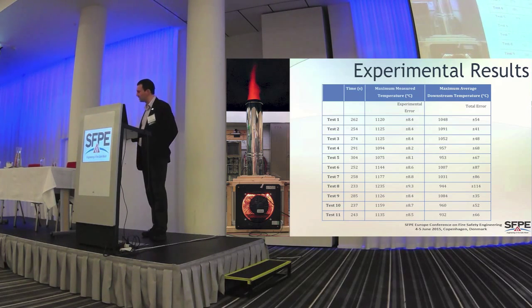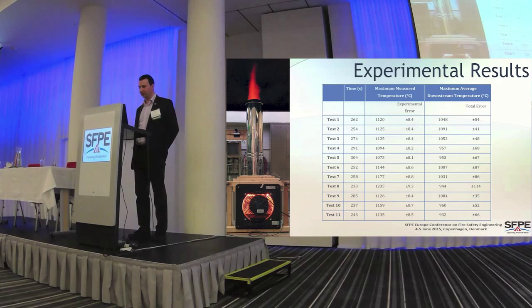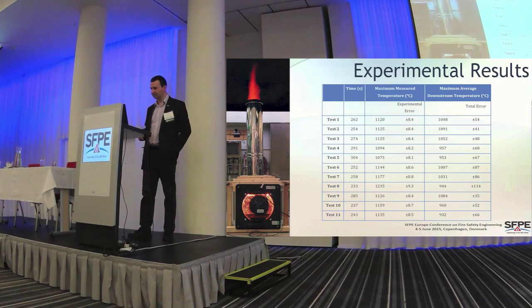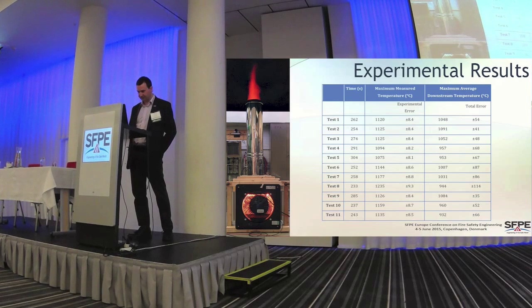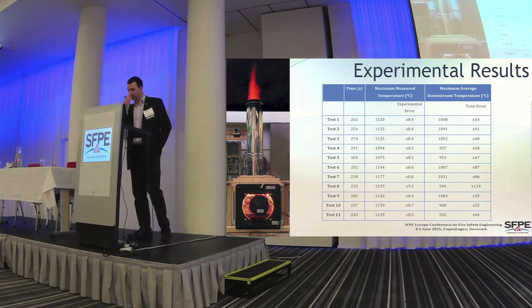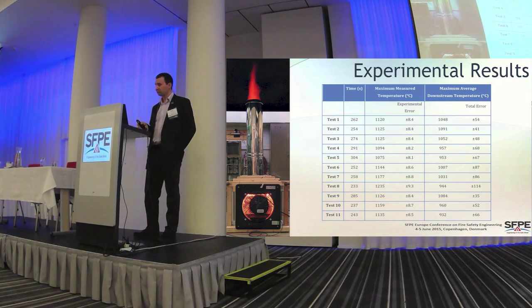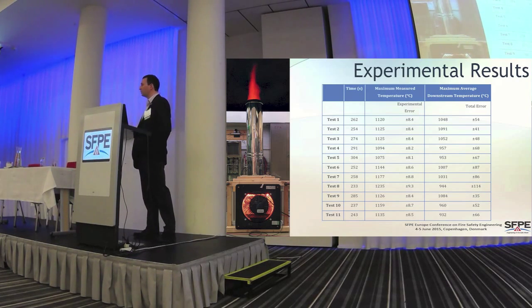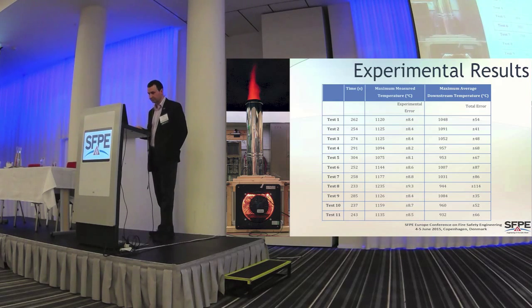But as you can see, the average temperature varied between about 950 through to about 1091, I think, in test 2. Yeah, 1091 in test 2 was the highest average temperature. So on the basis of this, we would expect that the outflow gases from these tests should always contain a small percentage, 2, 3, maybe 4% of oxygen coming out.